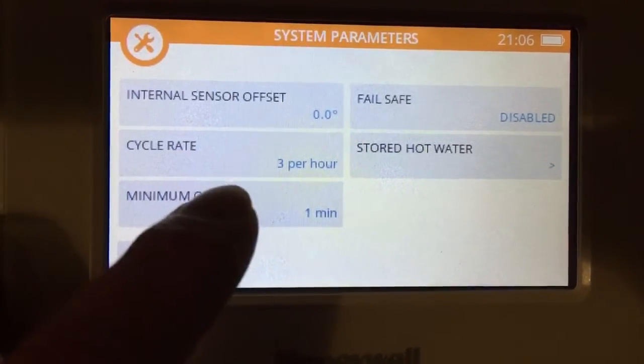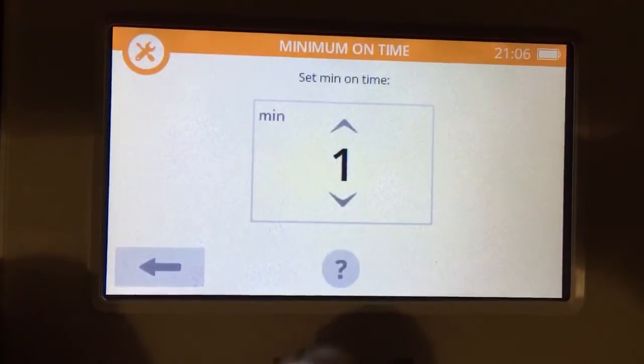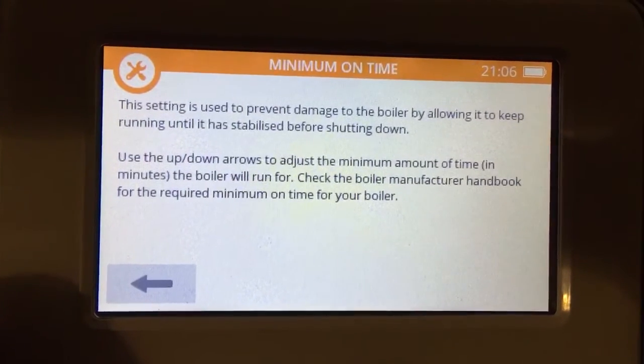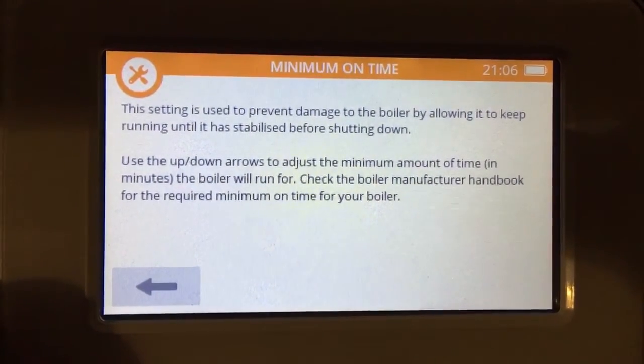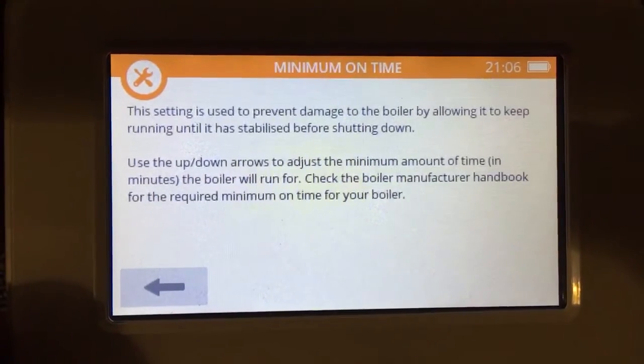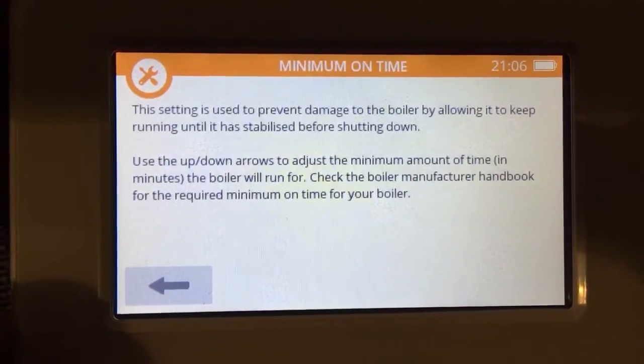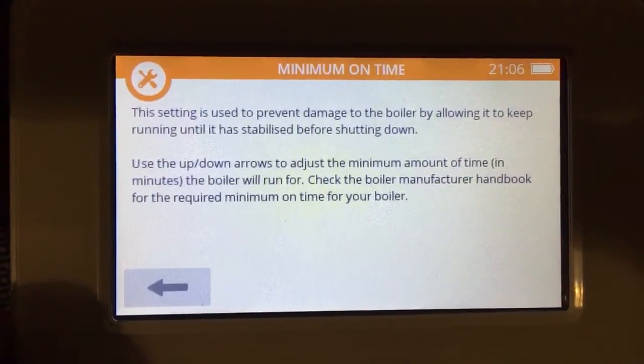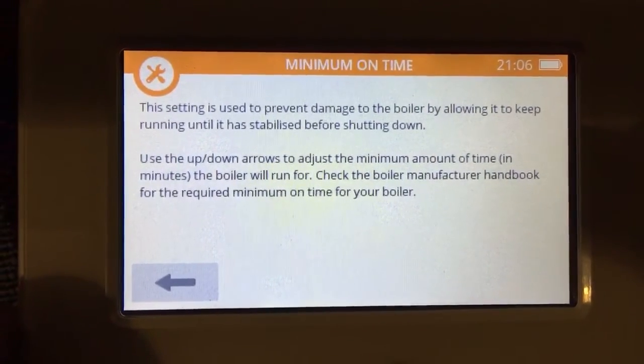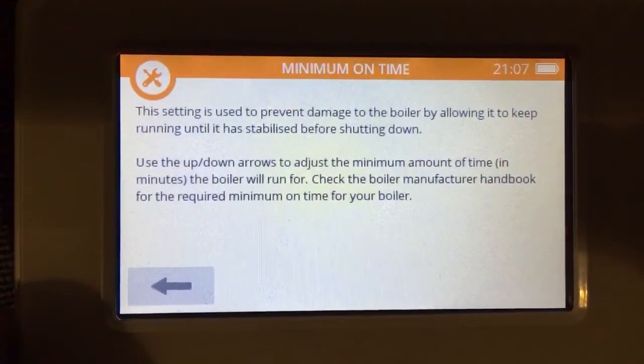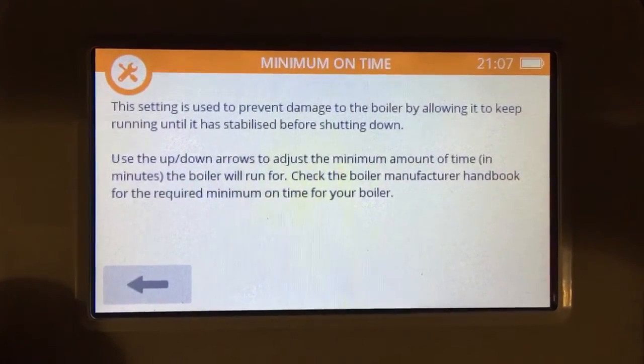Then looking at the minimum on time - touch it again. The question mark gives you your guidance. It's basically saying minimum on time is setting the minimum run of the boiler so that it doesn't short cycle, and you can run it for a minimum amount of time. This is important on things like oil boilers and heat pumps.